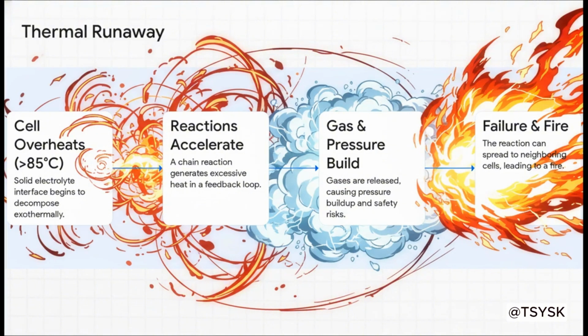And this is that something worse. It's a terrifying chain reaction called thermal runaway. See, if just one single cell overheats, and this can start happening around 85 degrees Celsius, a protective layer inside it starts to break down. This kicks off a self-sustaining chemical reaction that generates even more heat, which causes flammable gases to vent and pressure to build until you get a catastrophic failure. This domino effect is the exact scenario the BMS is designed to prevent.